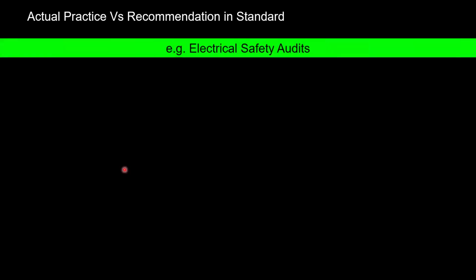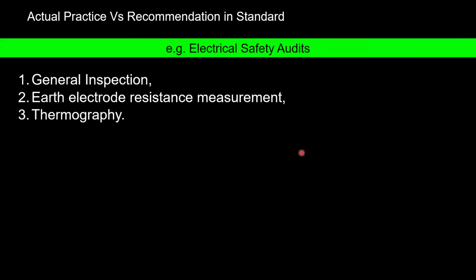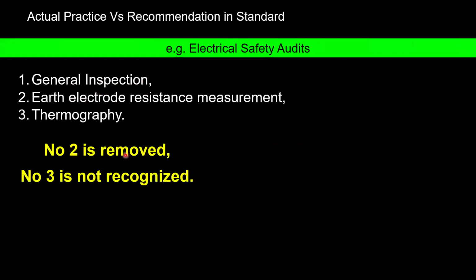Actual practice versus recommendation in the standard. For example, I am taking the electrical safety audit. In most medical locations or hospitals, electrical safety audits are done. For example, one day somebody comes, looks into all the panels, does a general inspection, walking from one end to the other end. Then they sometimes check the resistance of the earth electrodes, then they do thermography. This is the general practice, unfortunately.